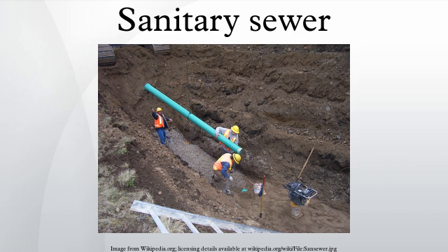Holding infiltration to acceptable levels requires a higher standard of maintenance than necessary for structural integrity considerations of combined sewers. A comprehensive construction inspection program is required to prevent inappropriate connection of cellar, yard, and roof drains to sanitary sewers. The probability of inappropriate connections is higher where combined sewers and sanitary sewers are found in close proximity, because construction personnel may not recognize the difference. Many older cities still use combined sewers while adjacent suburbs were built with separate sanitary sewers.